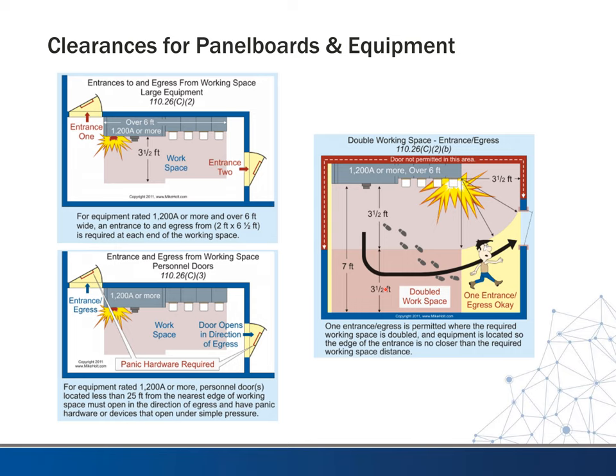So there is a special condition if you just can't get that second door and you still want to utilize this scenario, 1200 amps over 6 feet. The code does have an allowance that you can double the clearance in front of it. So instead of 3.5 feet in this case, we would need 7 feet total, so we'd have to double it. And the other condition is that the door itself can't be within this 3.5 foot radius of any part of the gear. So you couldn't have a door in this red area at all, right? Within the 3.5 feet of the space. So you have to get out of that space, right? In the blue space, we'd be okay to have a door. In the red space, we're not.